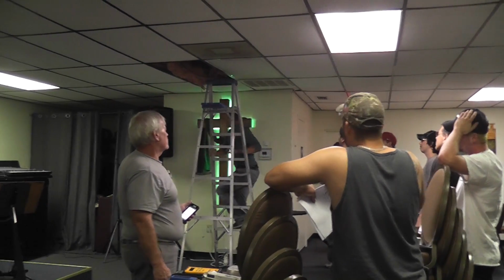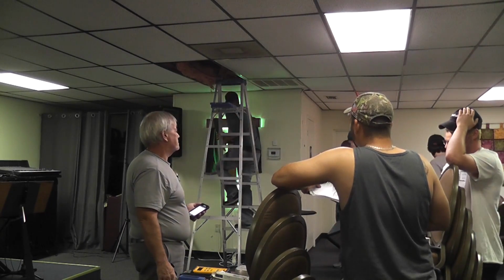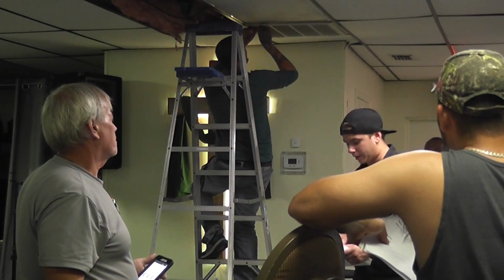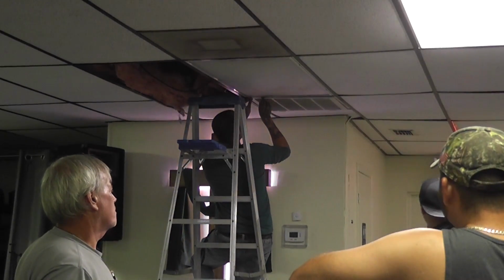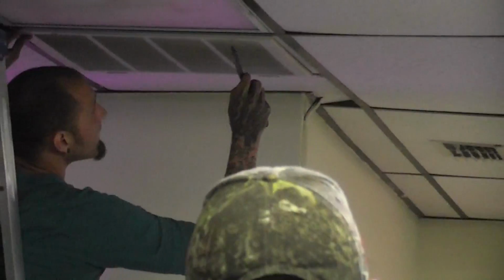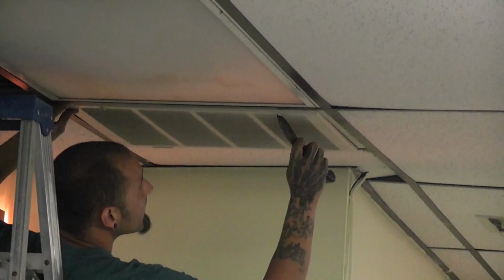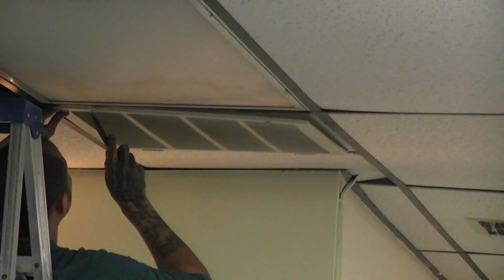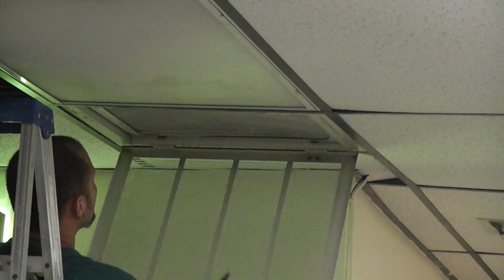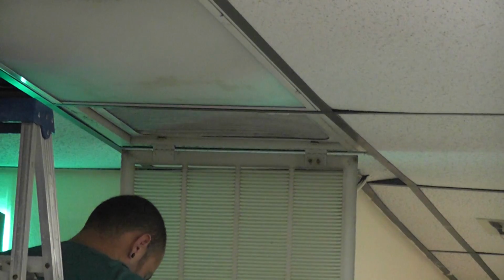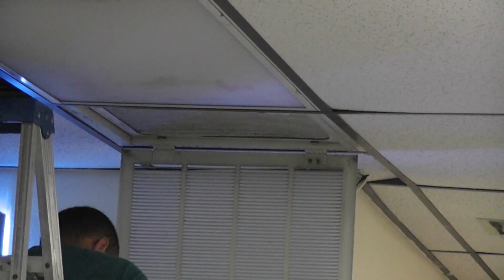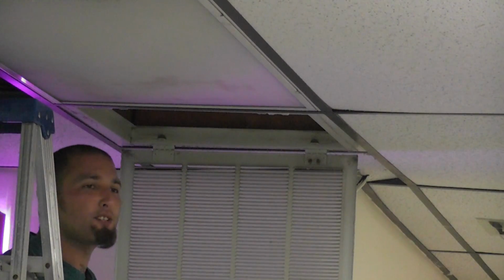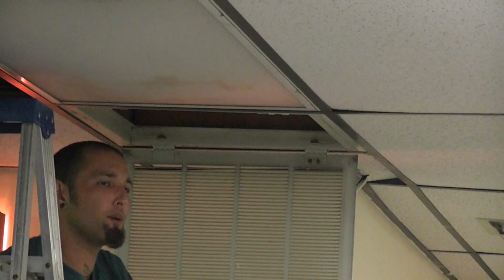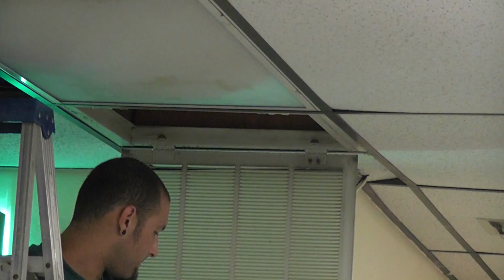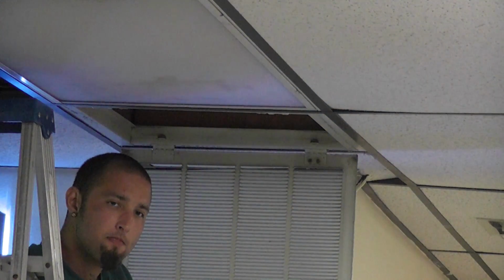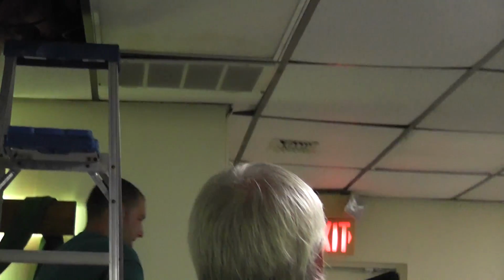So what's the model number of the unit outside? It's a Payne, and it's PA4NAN dash 7313. There's a bunch of different numbers. It's a 3-ton. How do you know it's a 3-ton? Because of the serial number. Look at it and say what size. There's certain 2 numbers in that serial number that's going to tell you the tonnage. This was made the 28th week of 2000. So we had 2575 before.